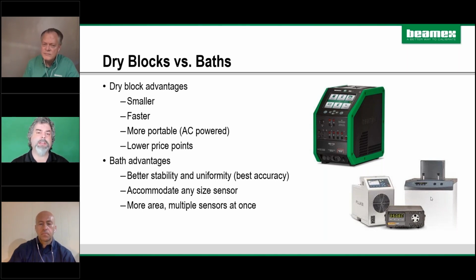If I could make a comment on the bath - normally you're looking at one bath per certain temperature. So if you're dealing with 2 or 3 temperatures, you're taking the probe and putting it in each bath, not ramping up the temperature generally. So the bath is more accurate, but slower, though you could do short sensors or multiple sensors. The dry block is cheaper and more portable.